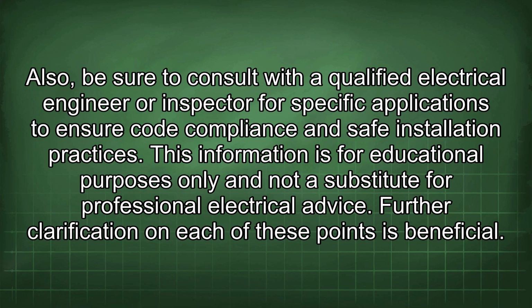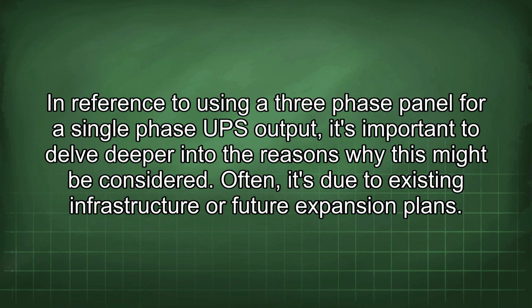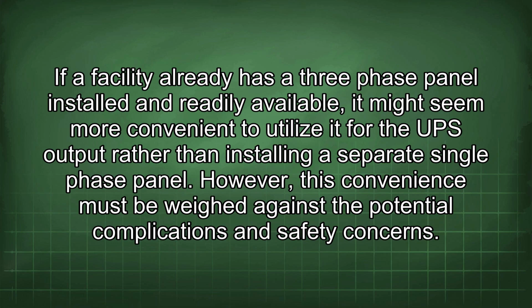Further clarification on each of these points is beneficial. In reference to using a three-phase panel for a single-phase UPS output, it's important to delve deeper into the reasons why this might be considered. Often, it's due to existing infrastructure or future expansion plans. If a facility already has a three-phase panel installed and readily available, it might seem more convenient to utilize it for the UPS output rather than installing a separate single-phase panel. However, this convenience must be weighed against the potential complications and safety concerns.